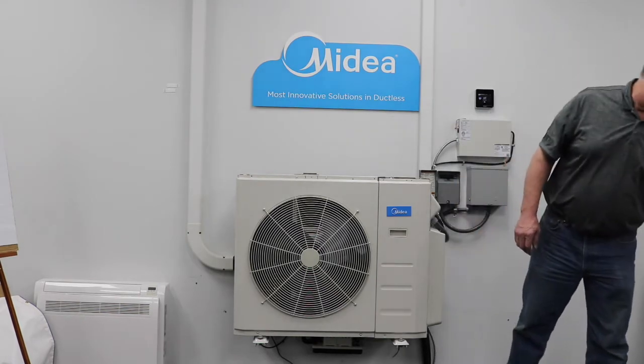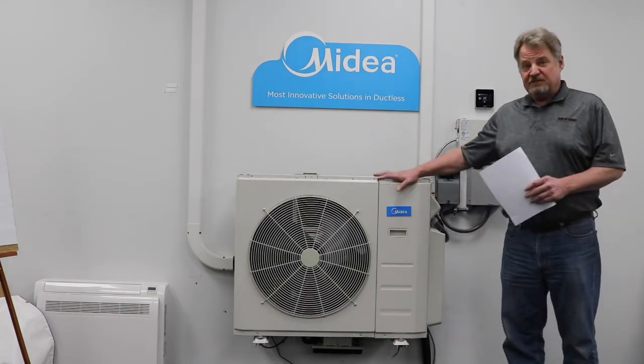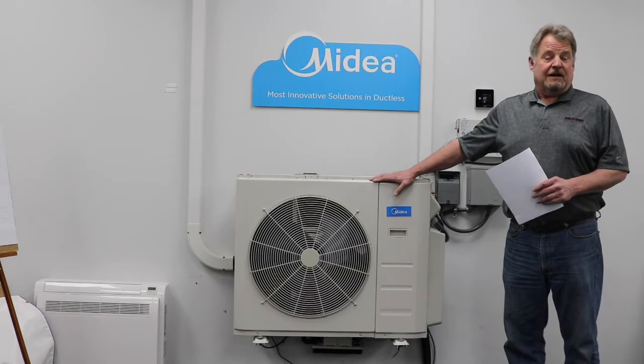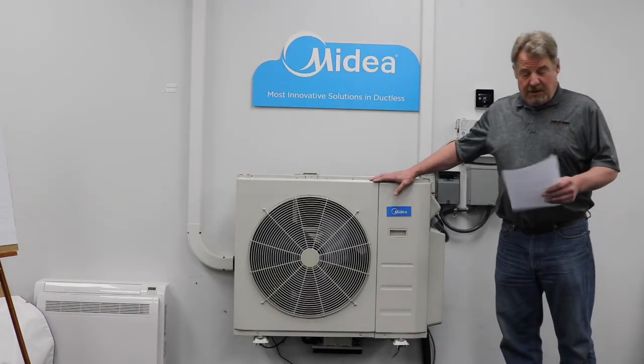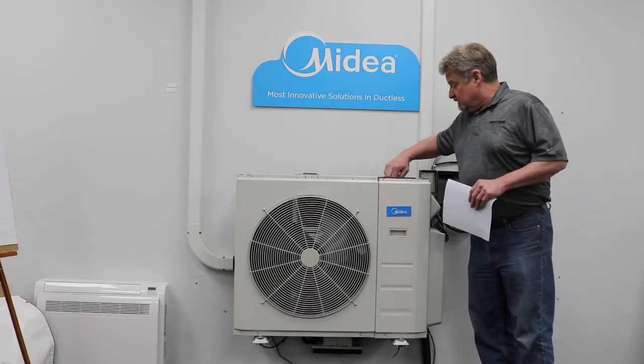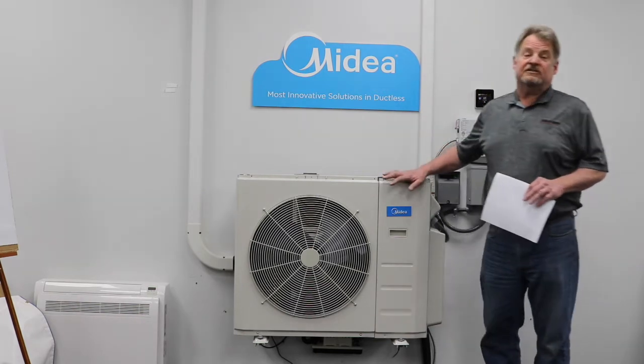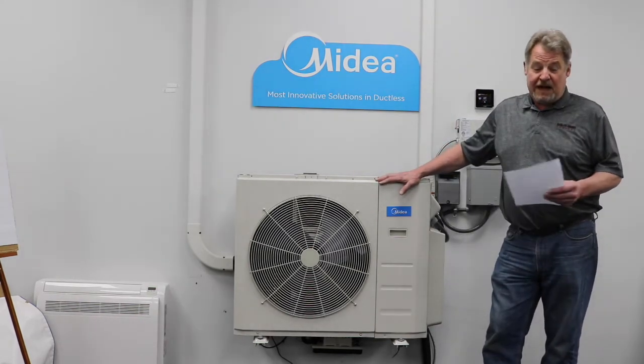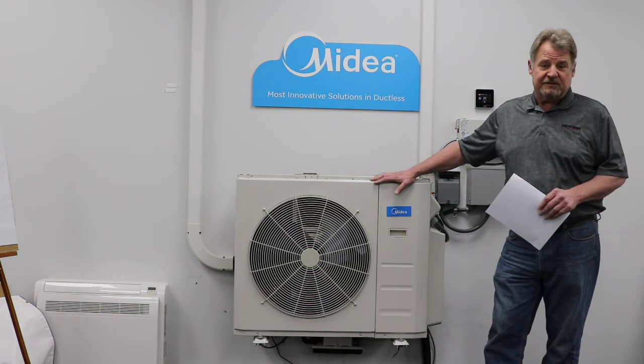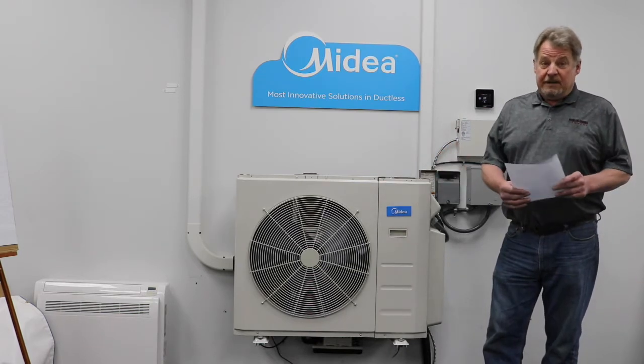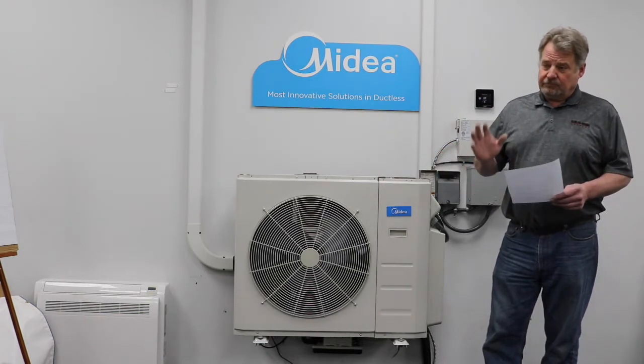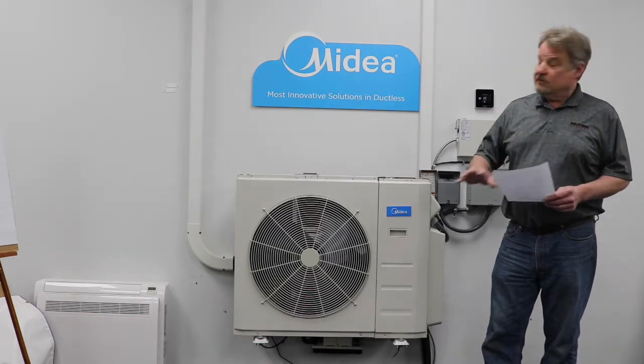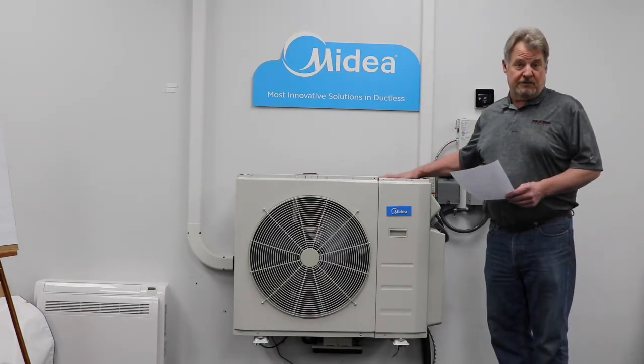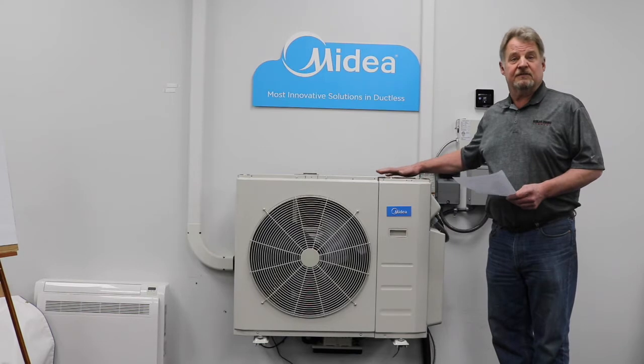Today we're going to do a little video tip on the digital display on the Midea Bryant multi-zone mini splits. There is a 2-digit digital display inside the multi-zones that allows us to do a lot of troubleshooting. Number one, in the event of a fault code, we'll have fault codes on the indoor units. We're also going to have a fault code on the outdoor unit. So we're going to come out here and see what the fault code is.